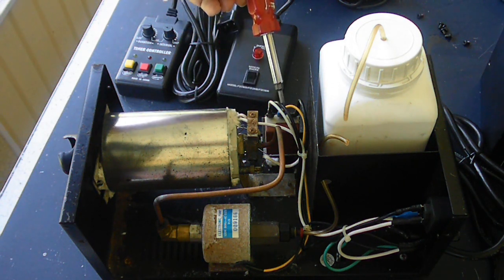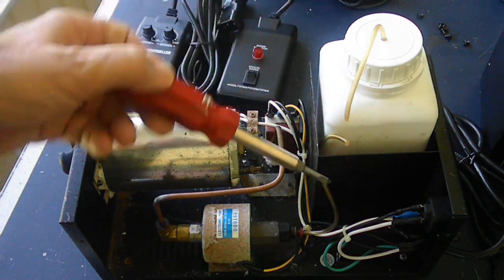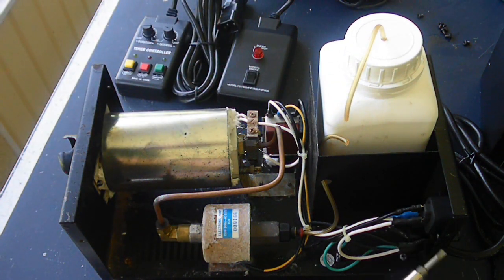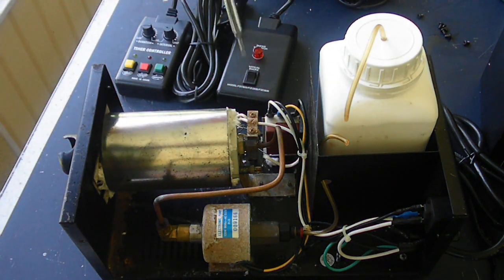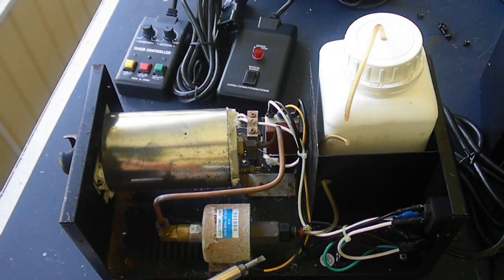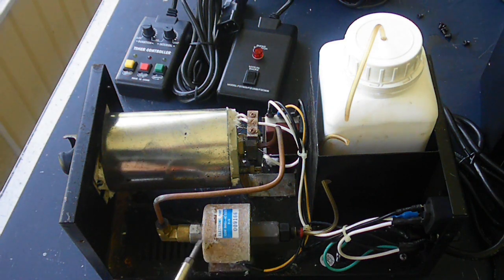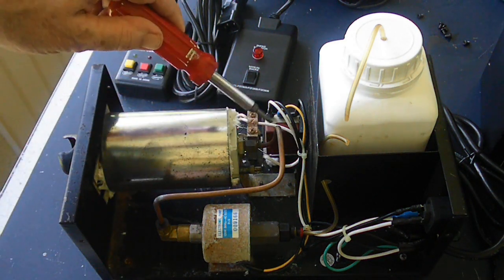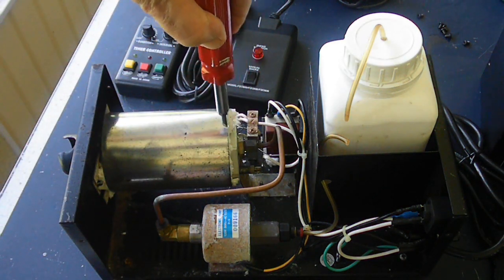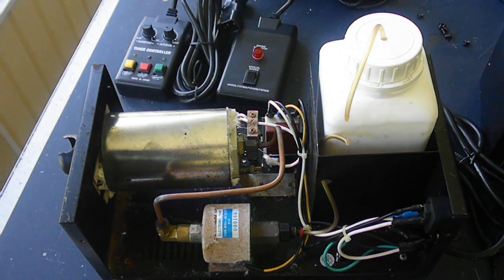A thermocouple will switch power from the heaters to this connector. This connector goes out and puts that 110 out to light the light, letting you know the machine is ready to operate. If you push this switch, it sends the 110 back into the pump itself, and it begins to pressurize fluid through this and force it through this passage, helping it to become vapor.